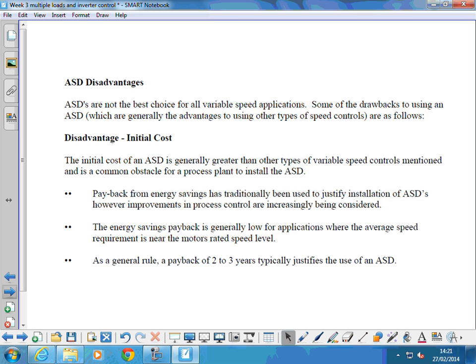But payback from energy savings has traditionally been used to justify installation. However, improvements in process control are increasingly being considered instead. The energy savings payback is generally low for applications where the average speed requirement is near to the motor's rated speed. So these energy savings we're talking about only happen if the motor's got a considerable time running at less than its rated output. If you're going to be running at synchronous speed, there isn't a lot. You're not going to get any energy saving. As a general rule, a payback of 2 to 3 years typically justifies the use of an inverter. Okay.